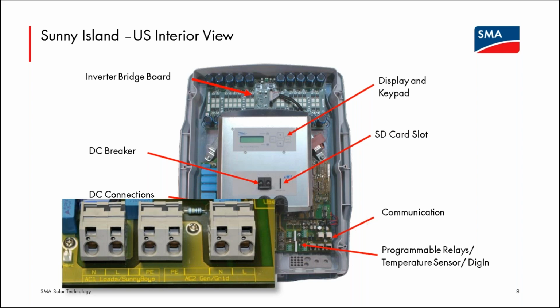This is another example of SMA's emphasis on AC coupling. I said that we would recommend the AC output of a PV inverter be on the loads panel that the Sunny Island is providing power to when it's in off-grid mode. So that is what we're wiring there on the circuit board. The loads and the Sunny Boy breakers should be there in that loads panel. So that's the AC1 and AC2 breakdown. It's right there on the circuitry.